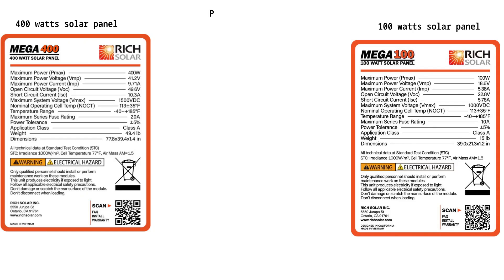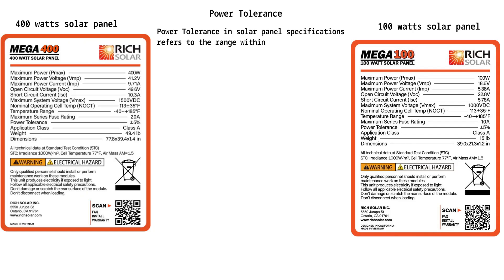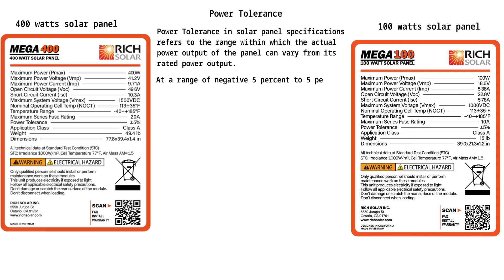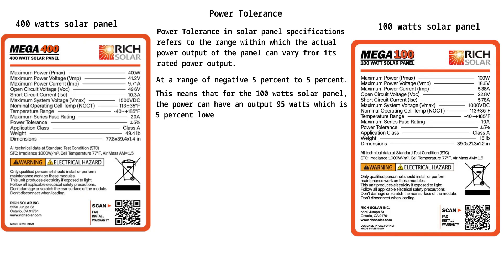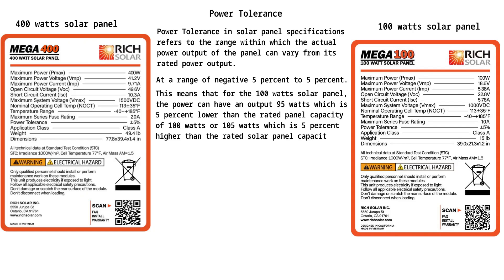9. Power tolerance. Power tolerance in solar panel specifications refers to the range within which the actual power output can vary from its rated output, at a range of negative 5% to positive 5%. For the 100-watt solar panel, this means output can be 95 watts (5% lower) or 105 watts (5% higher). Its role in the solar system is to help in system design and energy yield predictions. A lower tolerance ensures consistency and reliability in energy output.